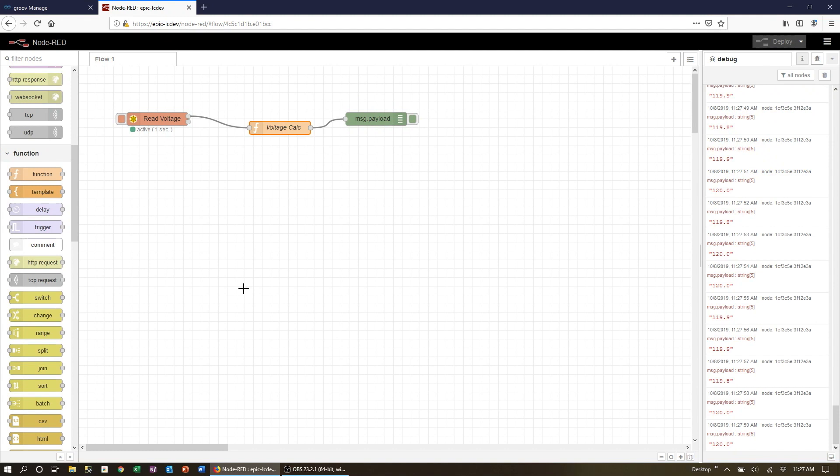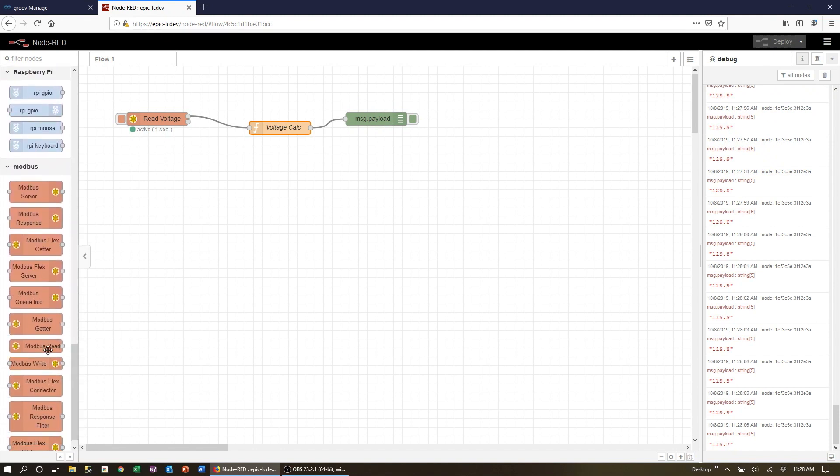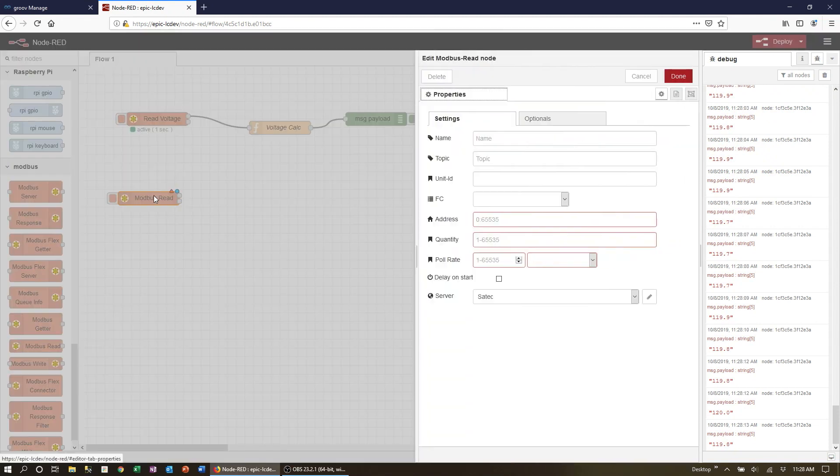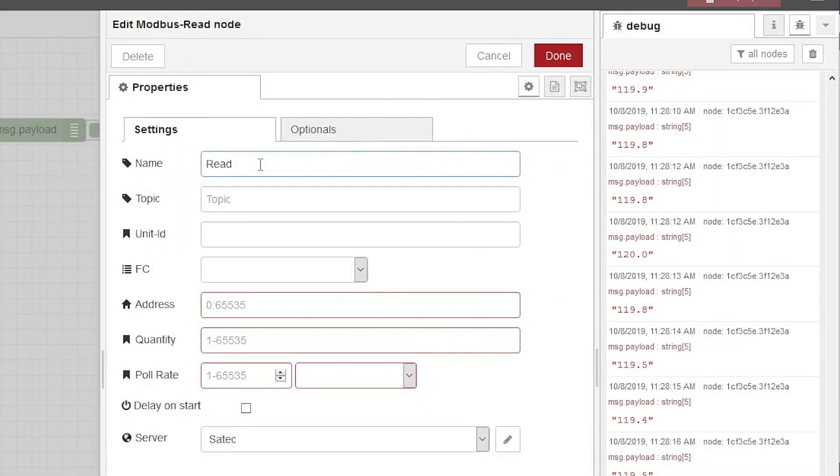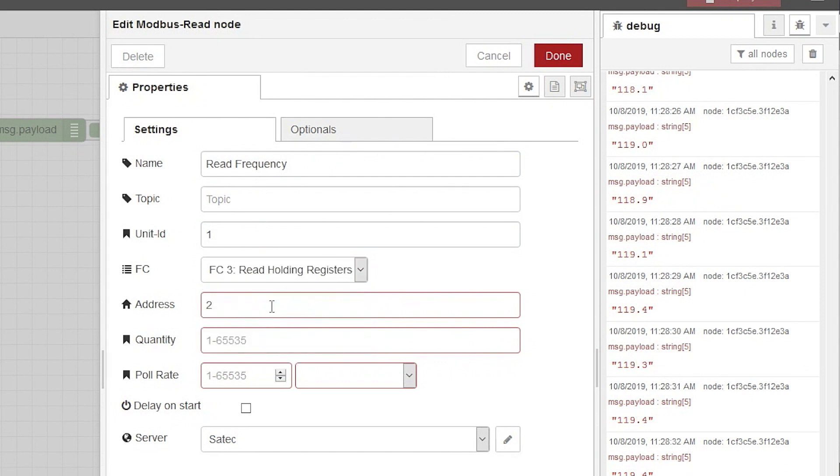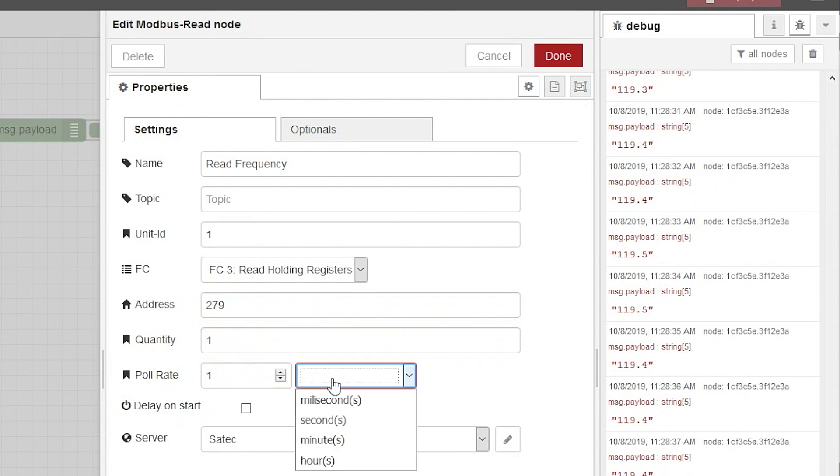Now let's do the same thing for frequency. We drag a read node over, double click to open its settings, give it a name, unit ID, select holding register. The address from the manual is 279. We want a single 16-bit number and again I'm going to poll the device at once per second. Notice that our SATEC device is already configured and is ready to go.